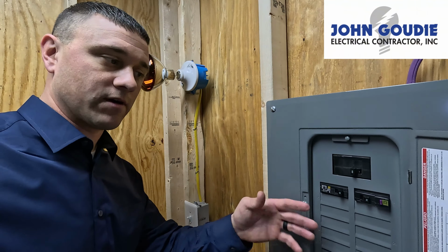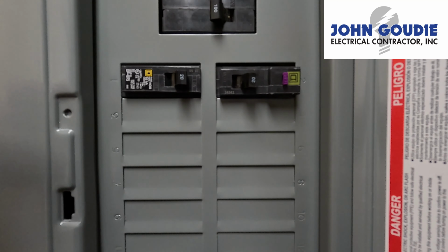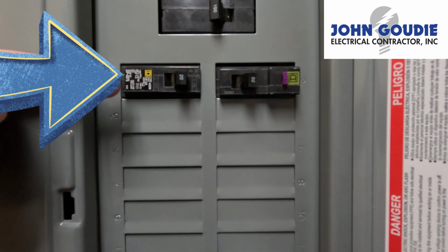So I kind of wanted to just go over what the differences are. Okay, so what we have right here, this is a regular circuit breaker. This is what you find in your good option for an electric panel upgrade quote that we provide you. So a regular breaker just protects against overdraw. For instance, this is a 20 amp breaker in this example, and this breaker would trip if you exceed more than 2400 watts of draw on this circuit. It's going to trip for that reason, and it would also trip if you had a dead short in the circuit or if the circuit got grounded out. So that's all a regular breaker does.